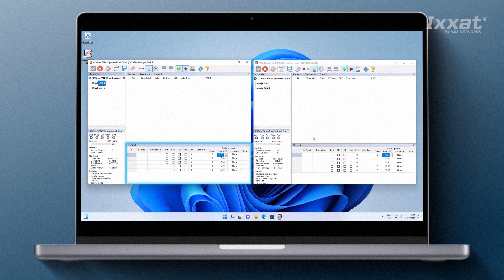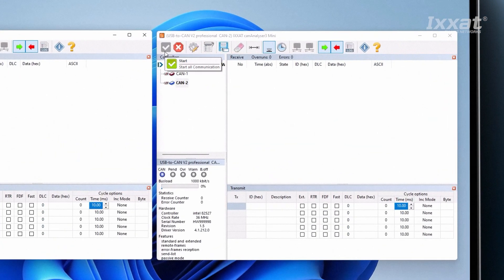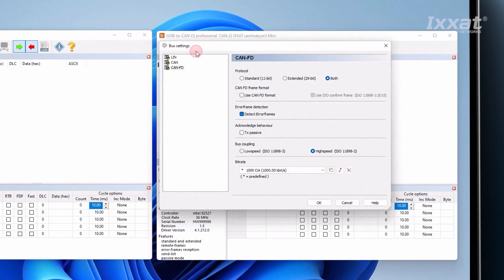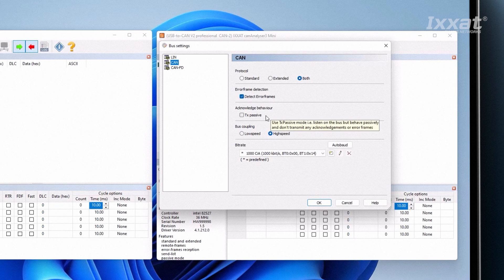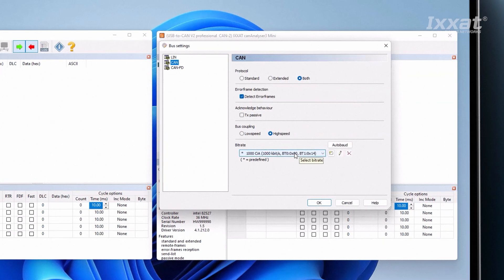Below the receive window is the transmit window where you can enter messages for single or cyclic transmission. On the top you will find the most important functions as buttons such as start, stop, and the settings for your device. Under settings you can change the protocol — either standard with 11-bit identifier, extended with 29-bit identifier, or both. You can also select whether to see error frames or not, and other options include the selection of TX passive mode for CAN and high or low speed bus coupling. At the bottom you can set the baud rate, where there is also an option for automatic baud rate detection.